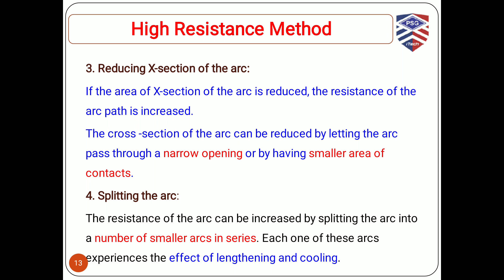And by splitting the arc, the resistance of the arc can be increased by splitting it into a number of smaller arcs in series. So we'll have a provision so that the arc will be split into many small arcs. By this method, we get the effect of both lengthening of the arc as well as cooling of the arc. So both effects are applicable in the last method, that is called splitting of the arc. These are the methods we have for increasing arc resistance for the purpose of arc interruption.